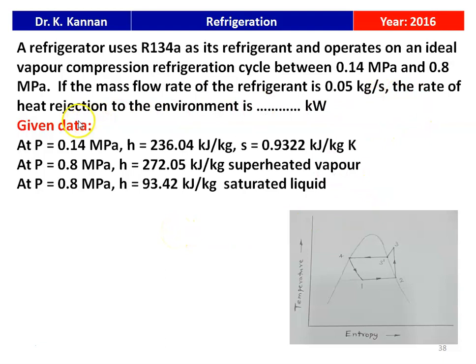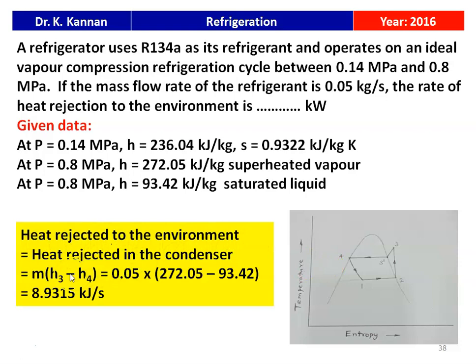We need to calculate the rate of heat rejection to the environment. Heat rejection occurs in the condenser, process 3 to 4. Heat rejected equals mass flow rate multiplied by (H3 minus H4), which is 0.05 multiplied by (272.05 minus 93.42), equal to 8.9315 kilo joules per second. The rate of heat rejection to the environment is 8.9315 kJ/s.